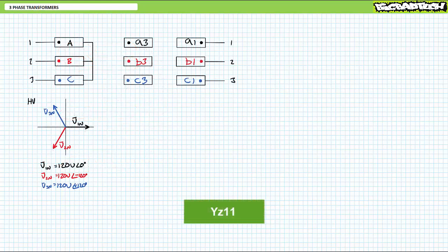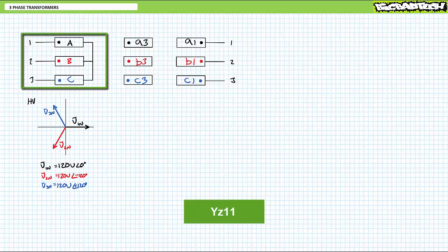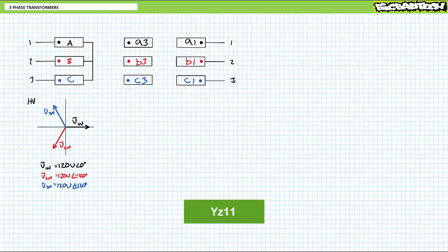Let's take a look at a random configuration like YZ11. At least the nomenclature is easy enough to interpret, now that you know how it works. The high voltage side is Y configured. The low voltage side uses a zigzag connection, which I'll explain in a moment, and low voltage side leads the high voltage side by 30 degrees. The high voltage side is configured like a standard Y with non-dotted terminals forming the central node of a Y. Too easy. Now comes the hard part.